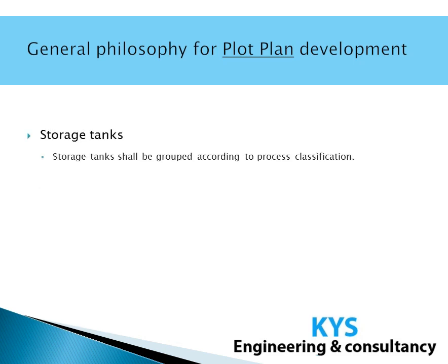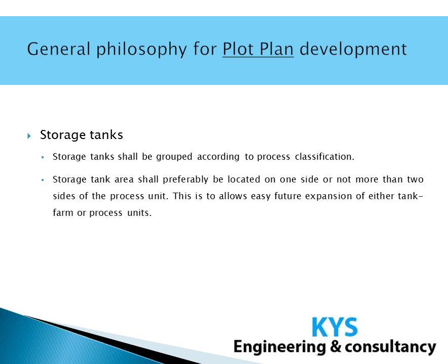Storage tanks. Storage tanks shall be grouped as per the process classification. We have certain classification based on the flash point of the process fluids, like class A, class B, class C. So storage tanks shall be grouped as per the process classification. Storage tank area shall preferably be located on one side but not more than two sides of the process units, because it will be easy for the future expansion of either tank farm or process unit.